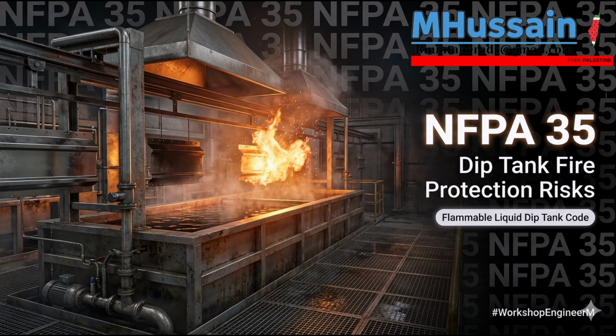So how do the sensors work? Modern sensors detect the loss of the ultraviolet or infrared signature of the flame and instantaneously shut off the main fuel supply. That's a lifesaver. And the physical area under the kettle where the furnace sits has to be completely curbed and sealed off from the main operating flow, right? Yes. Because they don't want a solvent spill from a totally different process running across the floor and pouring down into the open flame of the furnace. Exactly. Keep the fuel away from the fire.